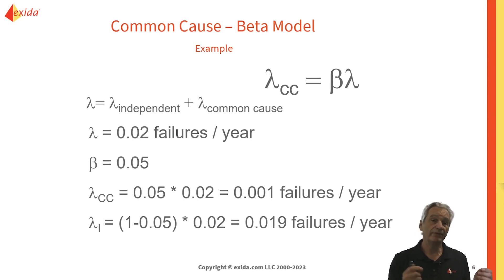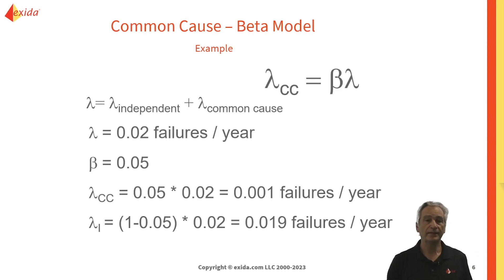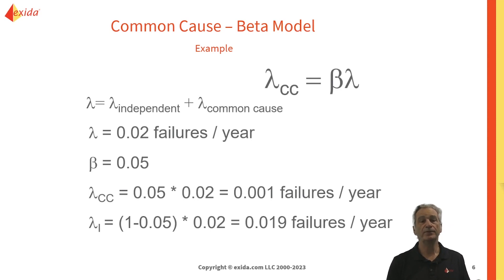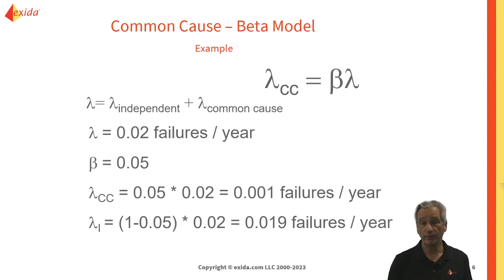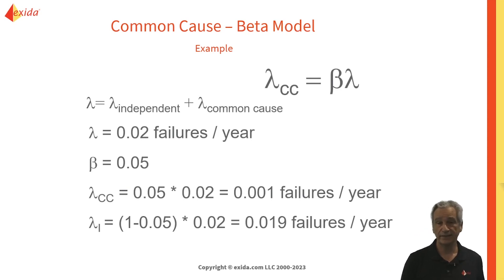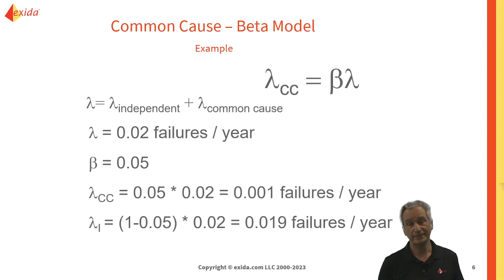To calculate the independent portion, we use the complement rule: 1 minus beta times lambda gives us our independent portion, which would be 0.019. Now if we've done our math correctly, when we add the independent and the common cause failure rates back together, we should get back to our original failure rate. So if we add 0.001 to 0.019, we get back to 0.02. That's a way of doing a sanity check to see whether we've calculated our independent portion correctly.